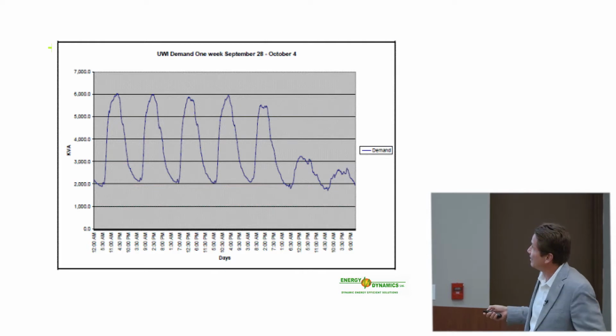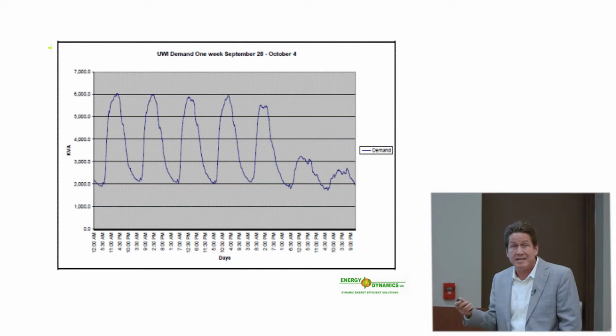So this is the load profile. During the night they'd go down to about 2 megawatts, and in the daytime up to 6 megawatts. This is the profile during the week, and on the weekend it looked like this. So you have to look at the load profile and analyze what you need.